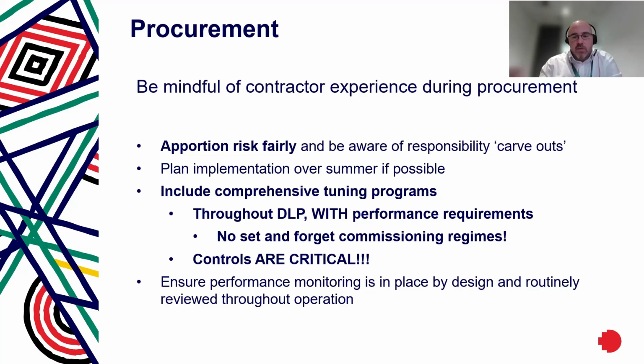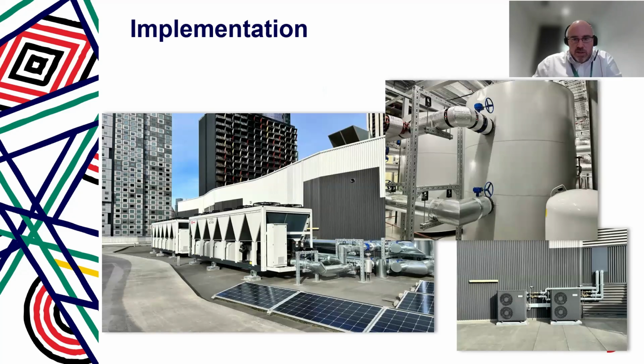And the intent there is, anytime the boiler comes on and starts to use gas, we need to have a look at the system and understand what we could do. Can we change some of the parameters to push that staging time out? Can we start the system a little bit earlier so that the boiler doesn't need to come on when people are arriving? The implementation is now done and operational, and this was the first major heat pump retrofit delivered in Melbourne CBD.